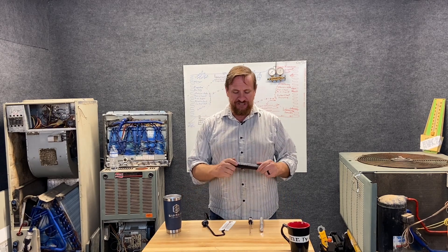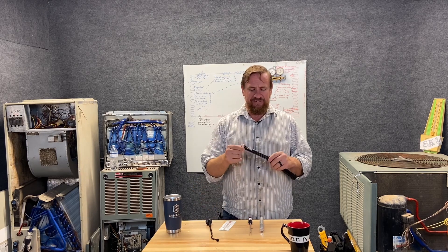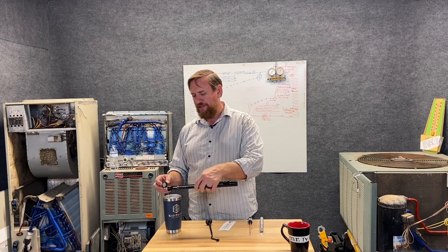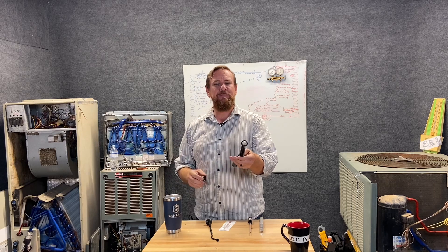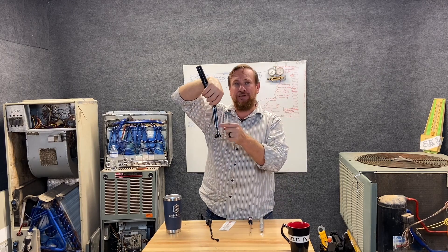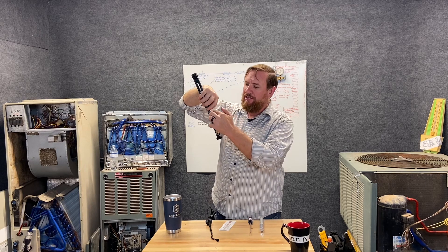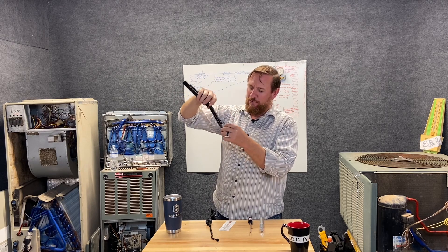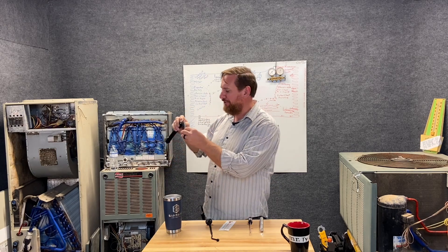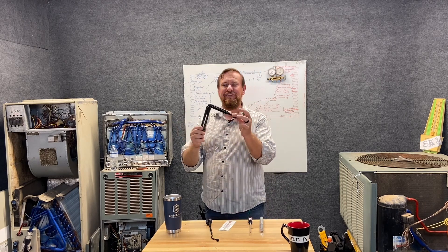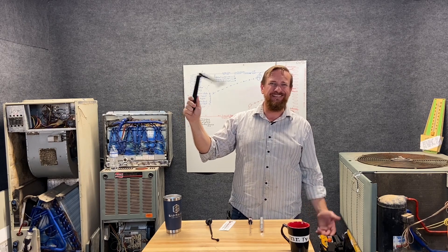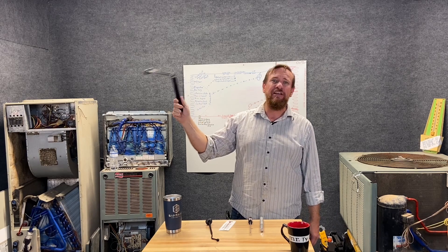Now in the older days, we actually had a thermometer. You could do it with this just like this, but we had to have these equipment here. And what we would do was we'd use distilled water. We weren't supposed to use just regular tap water, but we'd put distilled water. And in the very end, there's a piece of wick. So what we'd do is put the little cap on it. And we had two mercury thermometers. One was just a plain Jane thermometer, regular air temperature. The other one had that wet wick on it. And that wet wick had to be on the bulb just right. And in this case, it's not on the bulb anymore. Somebody probably pulled it off at one of the schools. But either way, what we would do is it had this little hinge on here. And we'd literally go into a customer's house and do this. Walk-in freezers or coolers, we would do this as well, but it would still freeze on that bulb. But still, it's very accurate when you use these.